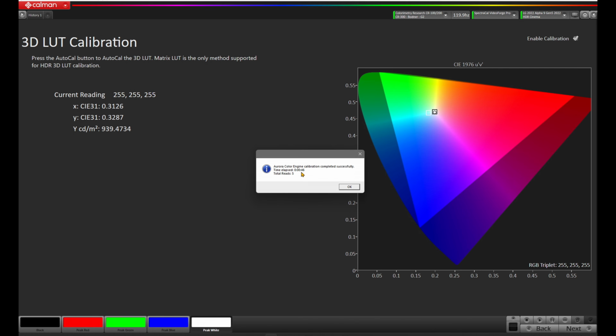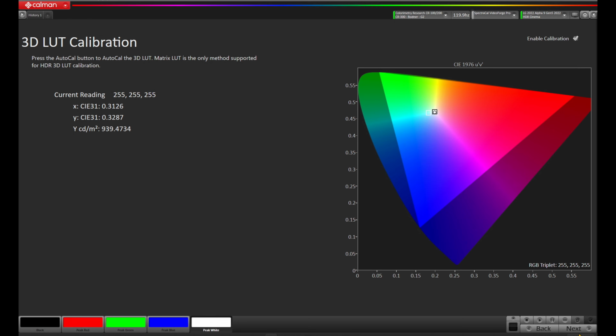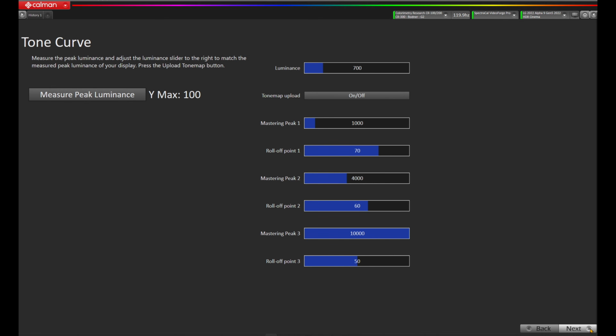Okay, so the matrix LUT is completed in about 46 seconds with a total read of 5. We're going to hit OK, and we'll press Next. Now, as I was just mentioning, we have the tone curve adjustment. So we can set max luminance by measuring it. So we can hit Measure Max Luminance.